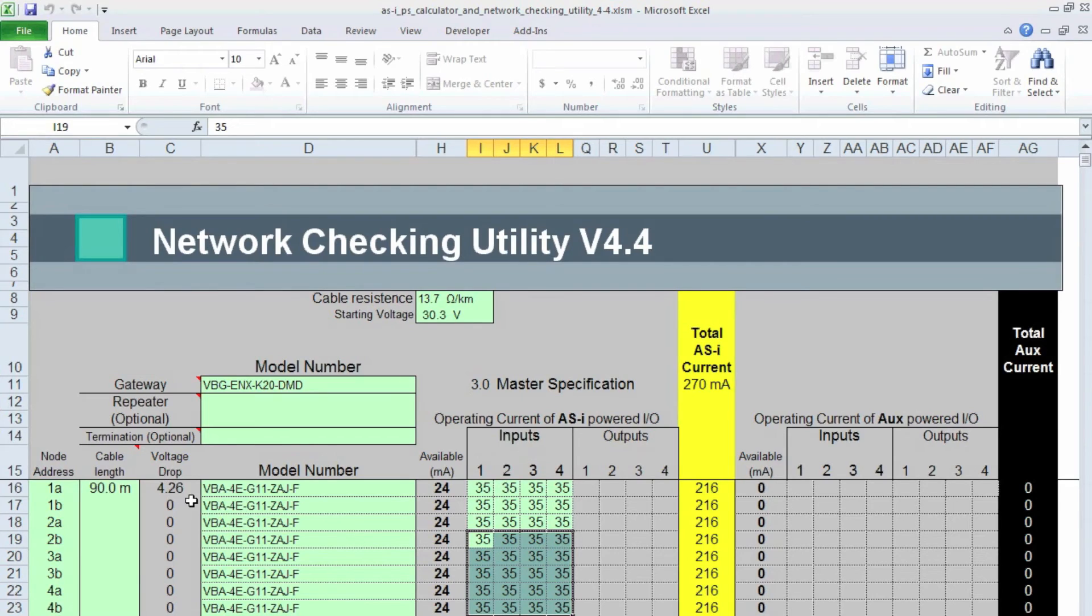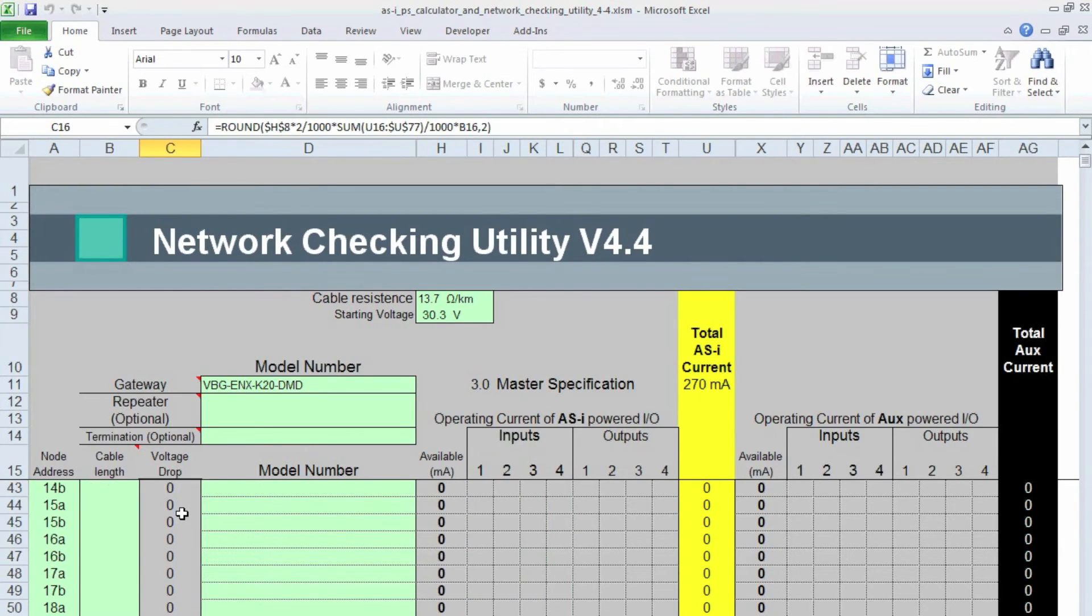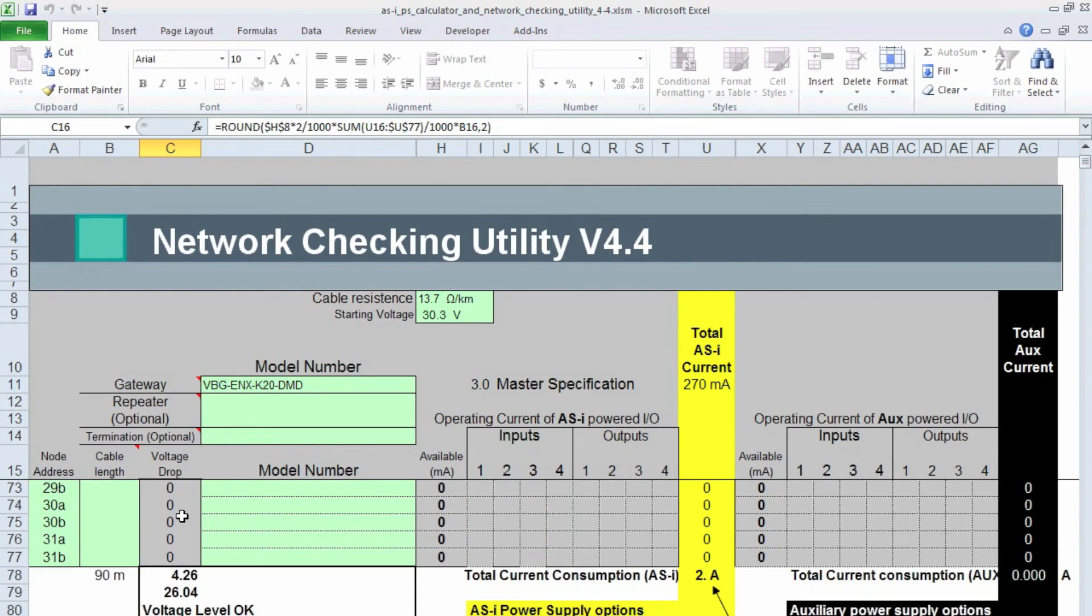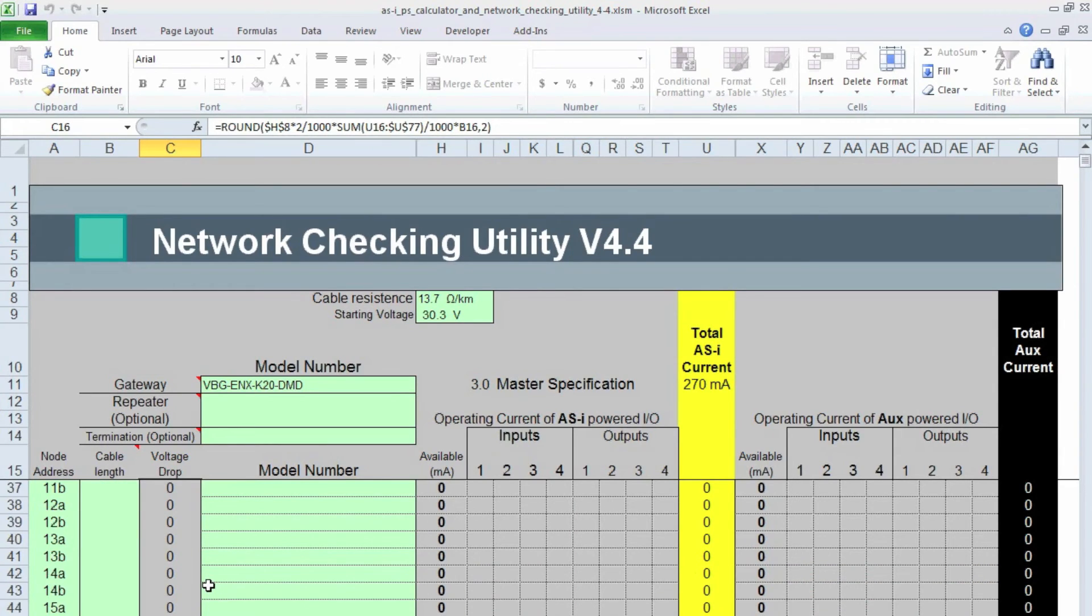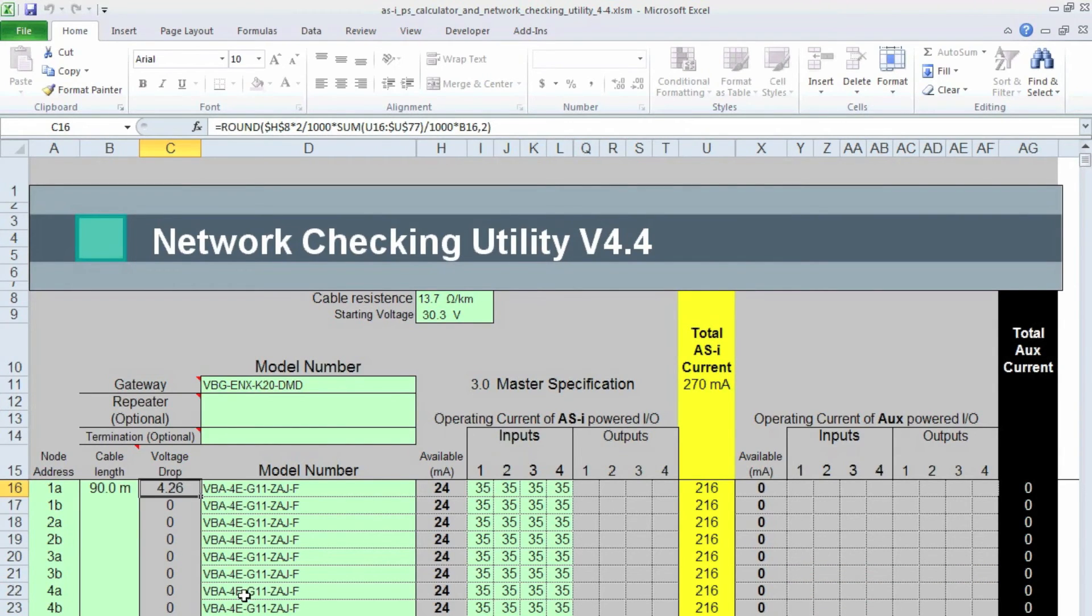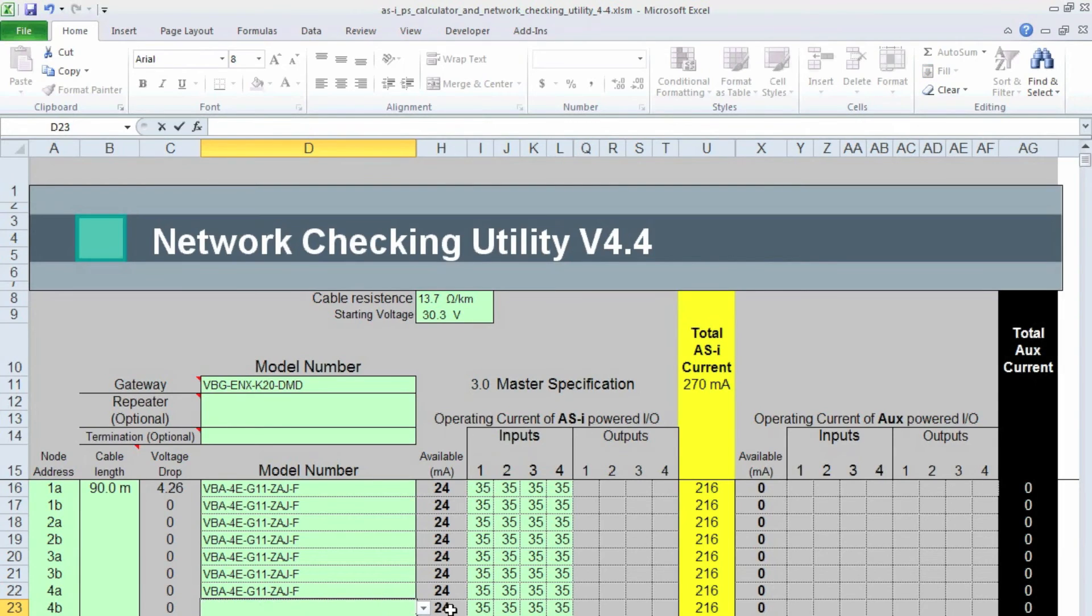Okay, so 4.26 volt drop. Seems like a little much. Let's confirm that. 26.04 is the end voltage, so that's too low. I am going to take one off.